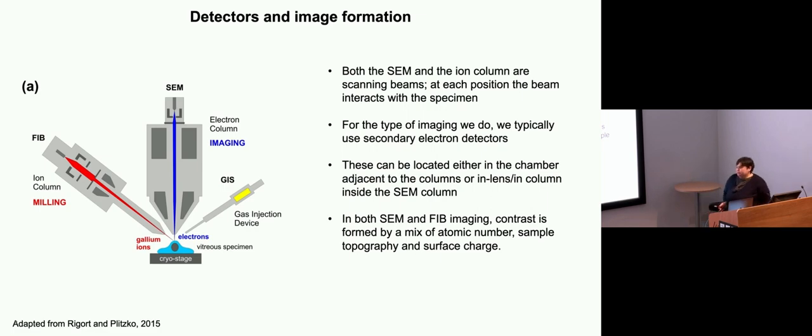Finally, I want to briefly talk about detectors and image formation, because this can sometimes cause some confusion, as we're used to thinking more about TEMs. Both the SEM and the FIB column are scanning beams. It scans across the specimen, and at each point it interacts. There are various scattering events that happen. You can have all sorts of different types of detectors. But for the type of imaging we do, which is generally fairly low voltage because we don't want to damage our lamellae before we do our tomography.